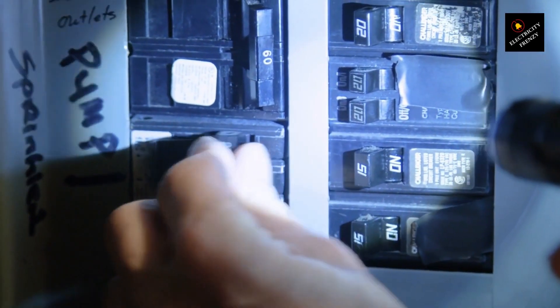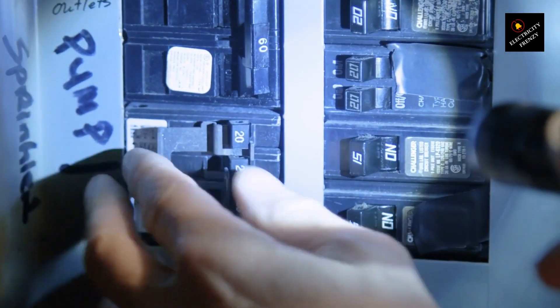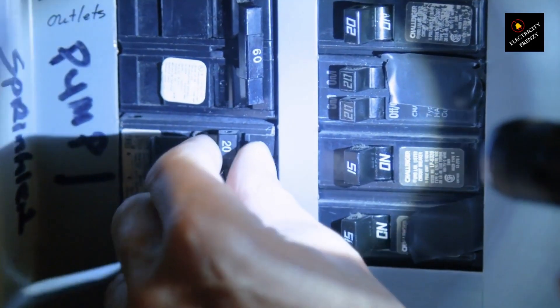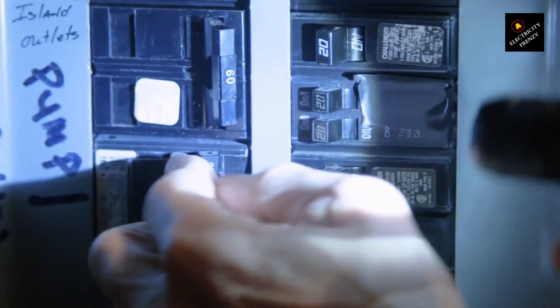Faulty wiring or loose connections. Loose electrical connections or faulty wiring in the circuit can generate resistance, resulting in heat buildup. This excess heat can trigger the circuit breaker to trip as a safety mechanism. Inspect the wiring connections in the circuit, ensuring they are tight and secure.